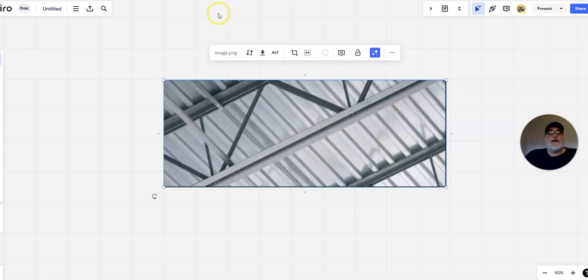Now, what we would do with this is run conduit in this zone right there. I don't know if you can see that with the color or not. Let's try that. We would run conduit basically above and right through here, in that little zone. What would happen when we do this is that the roofers would come along and run screws in all parts of this deck, because they lay the decking down, then there's insulation that goes over the top of it, and then the roofers put their screws through the insulation down into the decking. Well, they use 6-inch screws sometimes. Sometimes they don't need to when they have a thinner insulation. What that would do is run a screw right directly into our conduit, which would cause problems, which would cause failures.